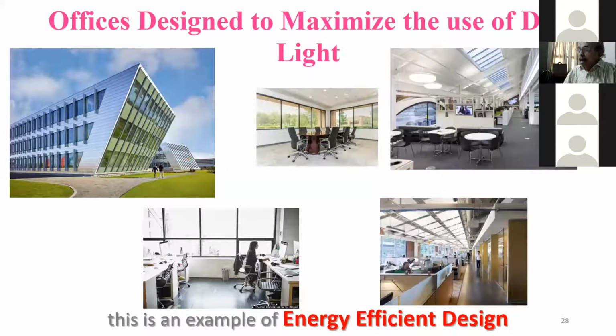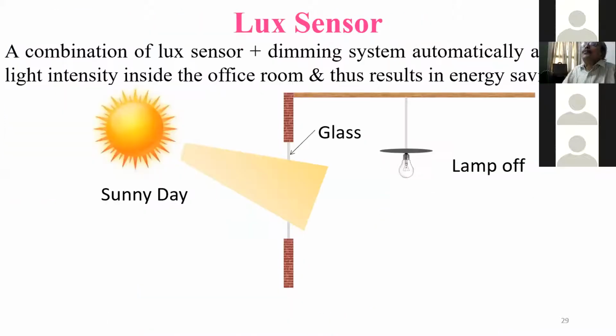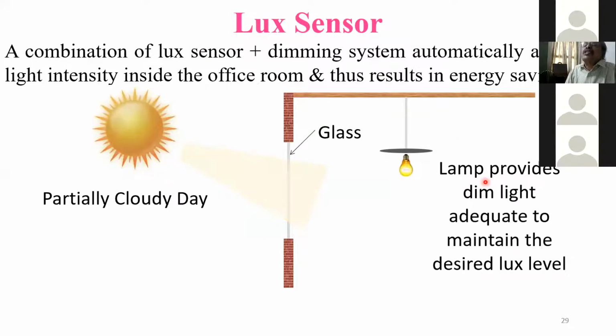No need for light. If you go for a combination of lux sensor and dimming system, it automatically adjusts the light intensity inside the office and thus results in energy saving. So if it is a sunny day, there is enough light inside the office, and automatically by lux sensor and the dimming system, the lamp is off. If it's a partially cloudy day, the lamp provides dim light adequate to maintain the desired lux level.